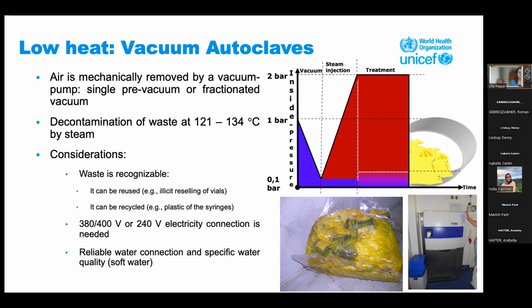Then you also have to keep in mind that this kind of technology is often using a three-phase electricity connection, so 380 to 400 volt, in most cases, at least for the bigger devices. The smaller ones, the tabletop ones, also work with 240 volt. But this is an electricity connection you have to provide. And it should be there on a reliable basis. And not all facilities do have this electricity connection available. Also, a reliable water connection and the specific water quality, soft water to protect the autoclave itself, is important. Next one.